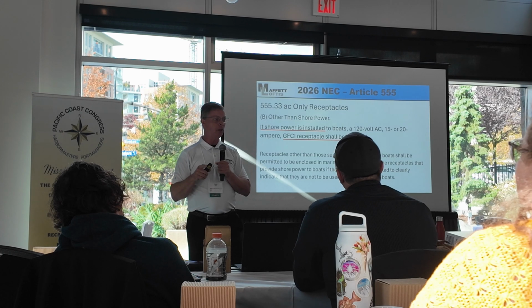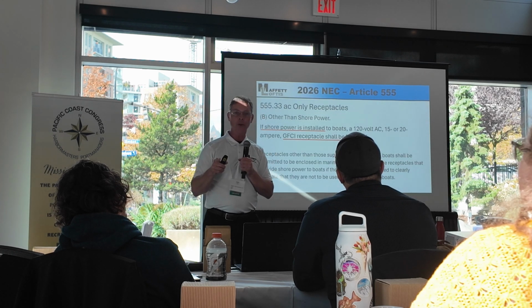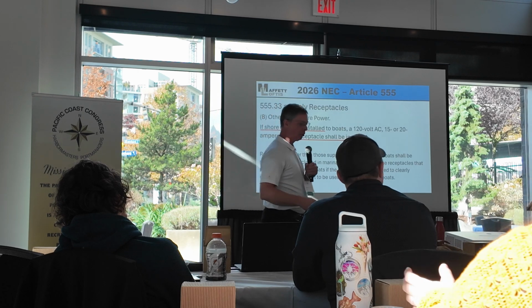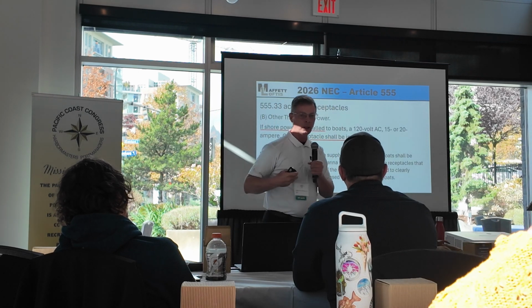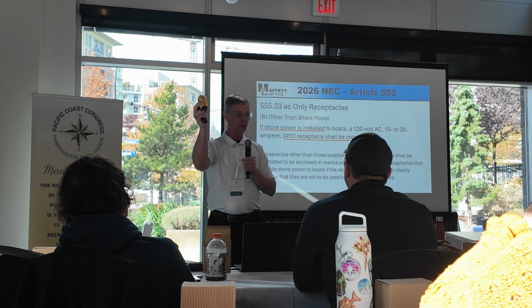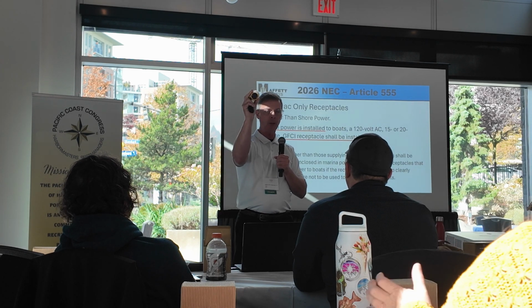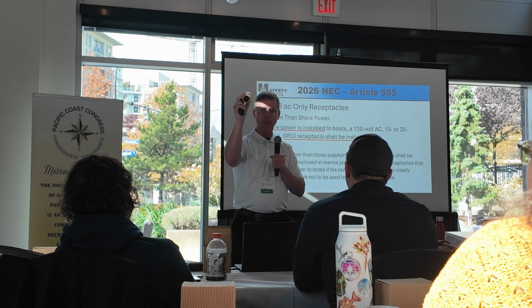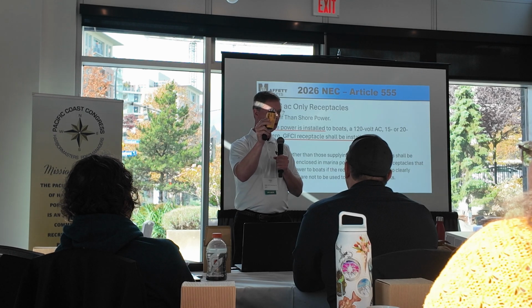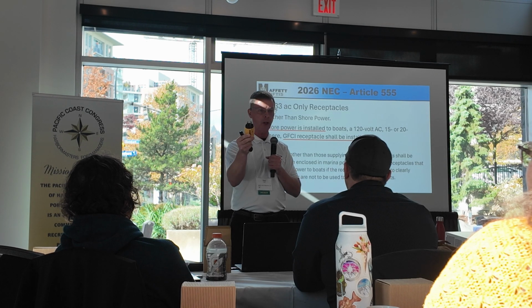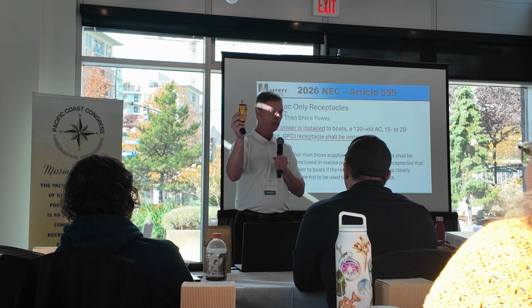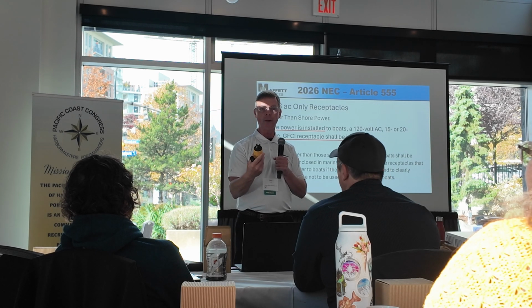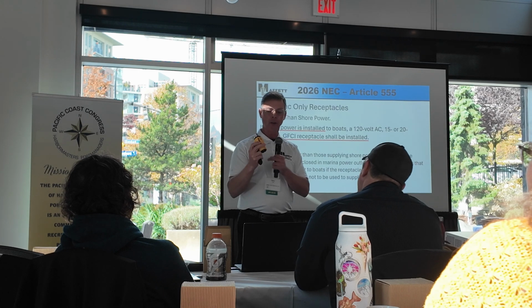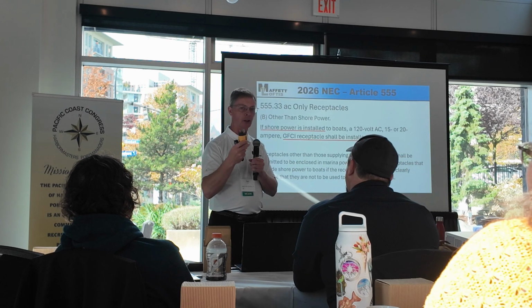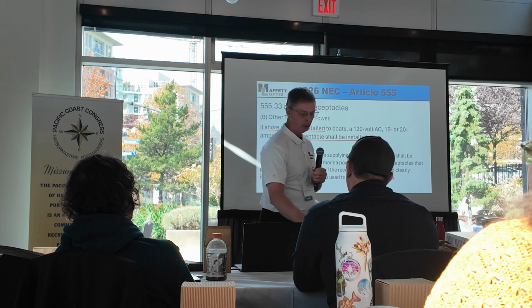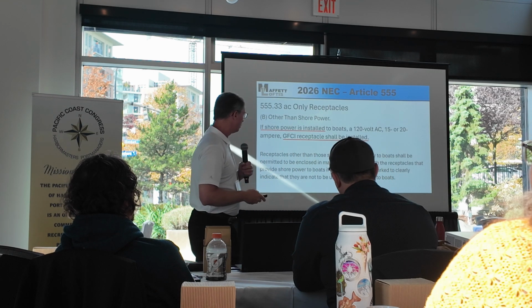And this right here is to alleviate extension cords and adapters and things that were just like I have right there. And this right here actually is a code violation. If you use something like this, or an adapter from 30 amp down to a 20 amp, it's a code violation. And actually this right here is not even listed for marina use. Even though Marine Code makes it, it's a 30 amp twist lock, it's not made for marina use. If you read the warning label on there, it's for RVs. And you have to have a 20 amp overcurrent protection, and it's always a 30 amp overcurrent protection. So that's a code violation to use those.